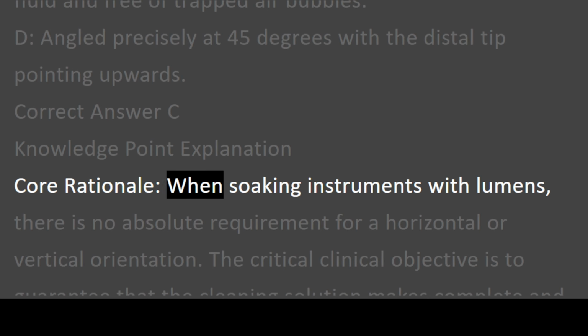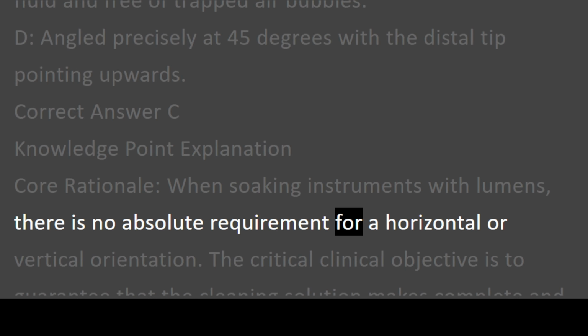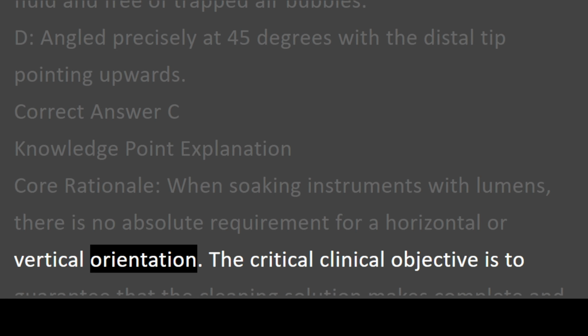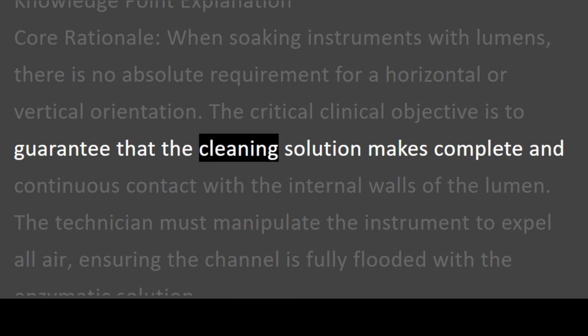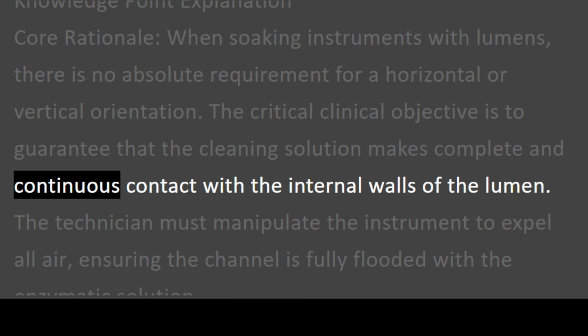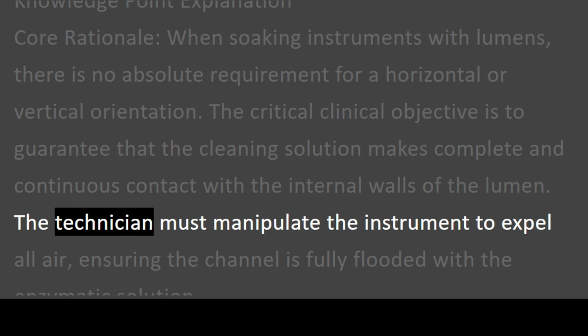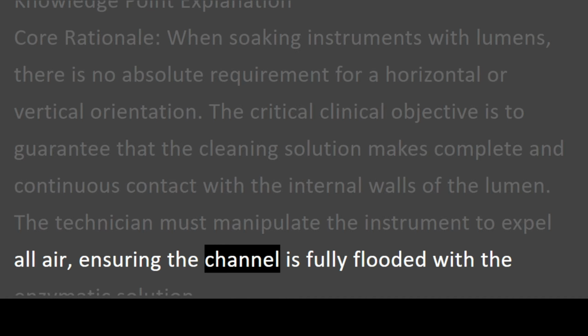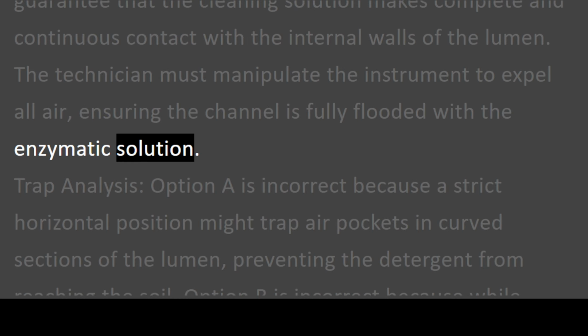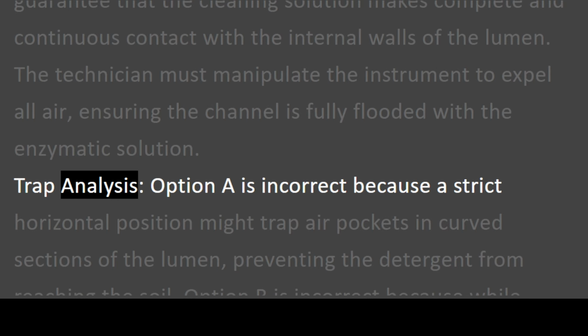Core rationale. When soaking instruments with lumens, there is no absolute requirement for a horizontal or vertical orientation. The critical clinical objective is to guarantee that the cleaning solution makes complete and continuous contact with the internal walls of the lumen. The technician must manipulate the instrument to expel all air, ensuring the channel is fully flooded with the enzymatic solution. Trap analysis.